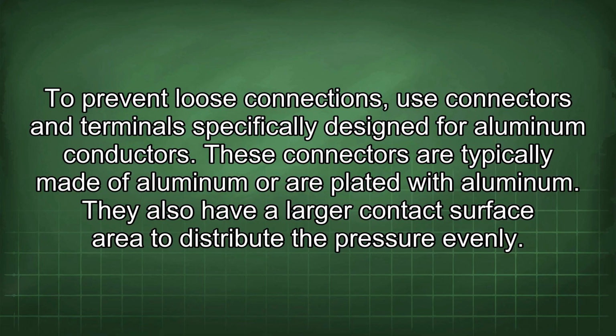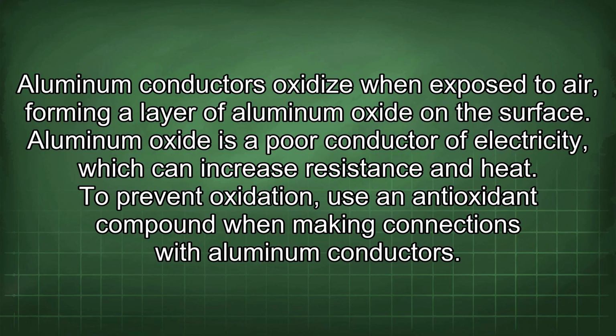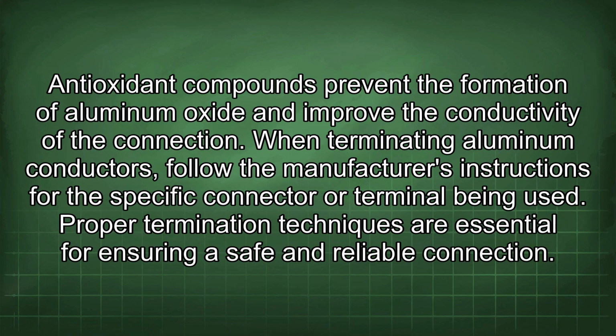They also have a larger contact surface area to distribute the pressure evenly. Aluminum conductors oxidize when exposed to air, forming a layer of aluminum oxide on the surface. Aluminum oxide is a poor conductor of electricity, which can increase resistance and heat. To prevent oxidation, use an antioxidant compound when making connections with aluminum conductors. Antioxidant compounds prevent the formation of aluminum oxide and improve the conductivity of the connection.